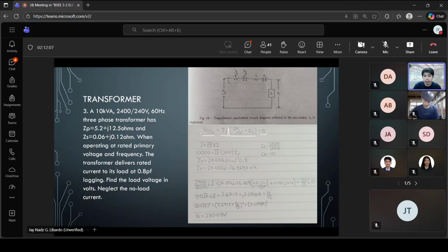After that, we get the equation by using KVL. Here we use IS because we are referring to the secondary, and we can solve for IS using the formula VL·IL. So 10,000 equals square root of 3 times... since we are referring to the secondary, we use 240 volts at the secondary, not 2,400. So we get a value of IS which is 24 amperes.